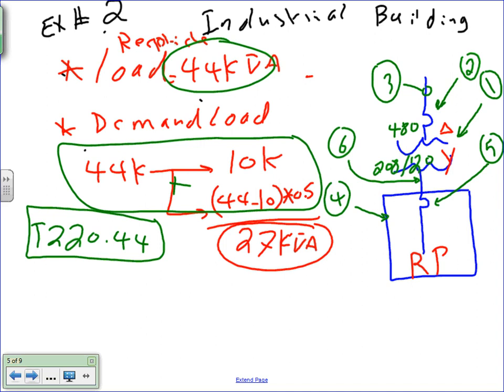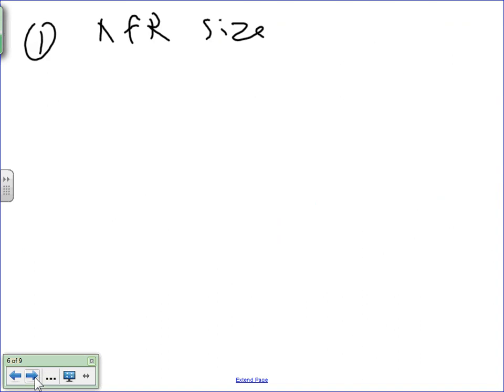Basically, if it's already demanded, you jump directly into sizing the transformer. Okay, any questions guys about this? So I need 27 kVA worth of power to feed my receptacles. That's all you care about. Cool? Okay, so we go to the receptacles.